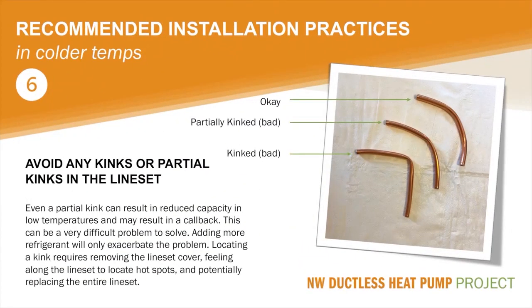Our next recommendation is avoid any partial kinks in the line set. Even a partially kinked line set can result in reduced capacity in low temperatures and will likely result in a system with ongoing service problems. Partially kinked line sets can be very difficult to troubleshoot because there are no error codes generated by the system. It is something to look for when a customer reports that their ductless system isn't able to make enough heat when it gets below freezing, yet you were sure you picked the right capacity system for the job.